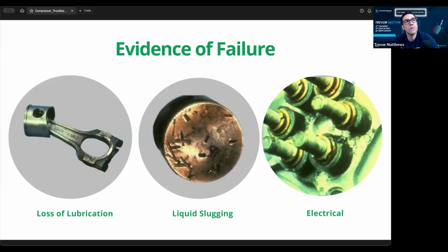Awesome. Okay, what are some of the causes of overheating? We talked about it already, you've got high suction, you could have a really hot head on it. What are some of the things that cause compressors to overheat? Dirty condensers mainly. If you have a dirty condenser, it's going to overheat there, and just broken parts. Also, your relief valves in there are set to pop off at about 350 psi. But yeah, overheating is a big problem. But maintenance, everything that we talked about, a good preventive maintenance system will help you.